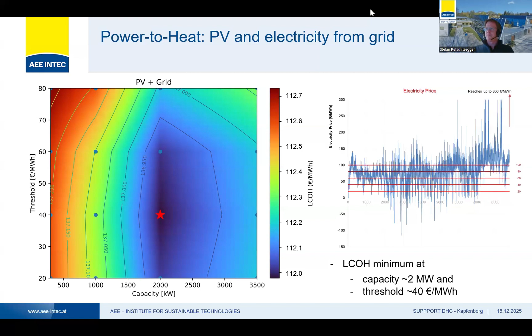The important thing here is really to take into account all the costs related to this system, be it CapEx, OpEx, or funding, as we heard from our Lithuanian colleagues before. In our case, the different calculations and results showed that a capacity of roughly 2 megawatts would make sense in Kapfenberg, and it would make sense to buy electricity from the grid if the price is below 40 euros per megawatt hour. This would decrease the overall heat production costs.